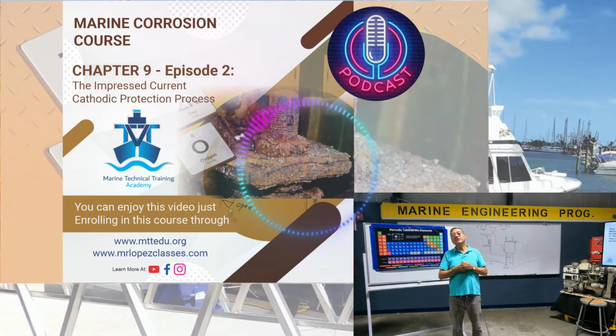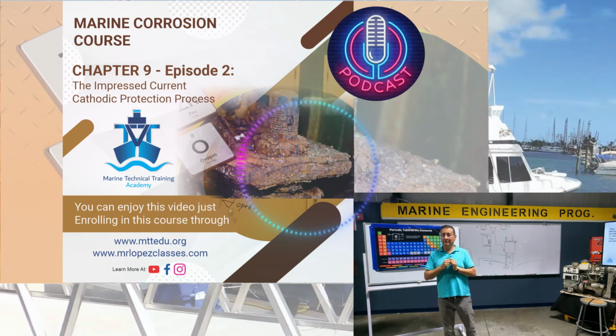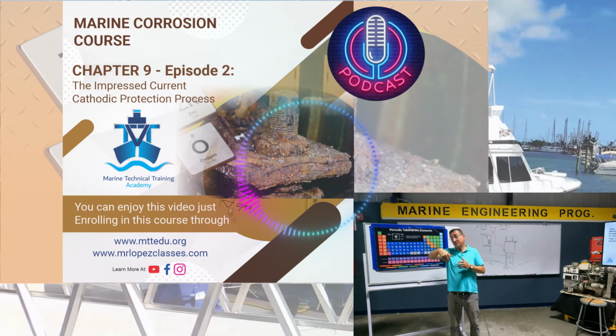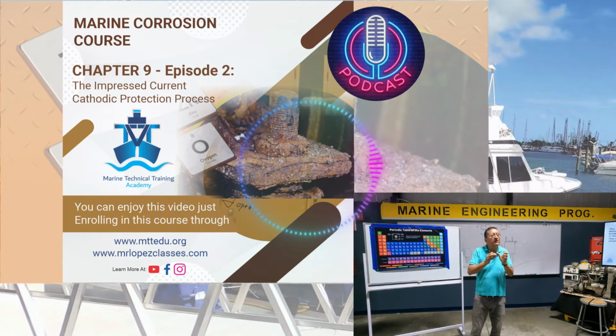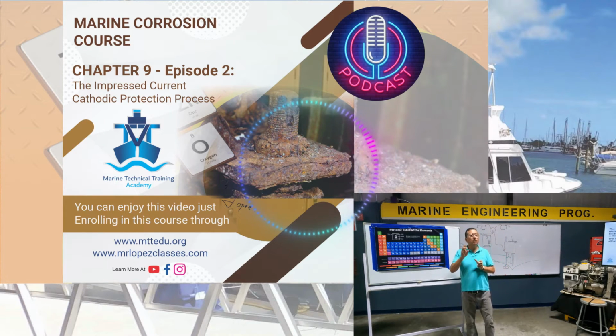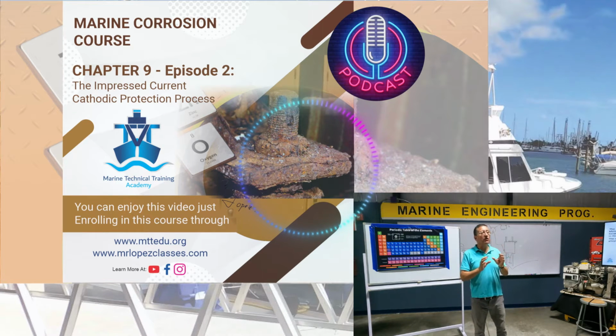Yes? Okay? It's clear. Until today we have the sacrificial anodes and a new system, the impressed current cathodic protection system. We are going to try to understand what is the meaning of that and how the impressed current cathodic protection system works. I explained that the secret is the element that produces the source of DC current, because we are going to send a DC current. The impressed current cathodic protection system is an external DC current controller, and that element applies a flow of electricity into the pipe, into the structure that you want to protect.